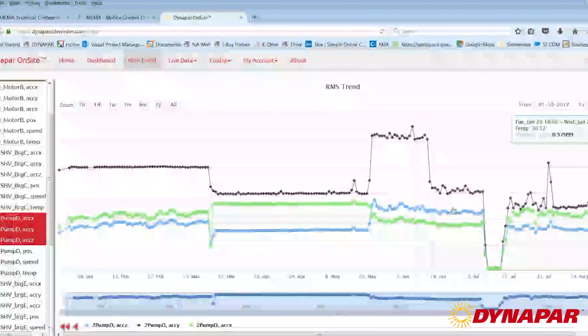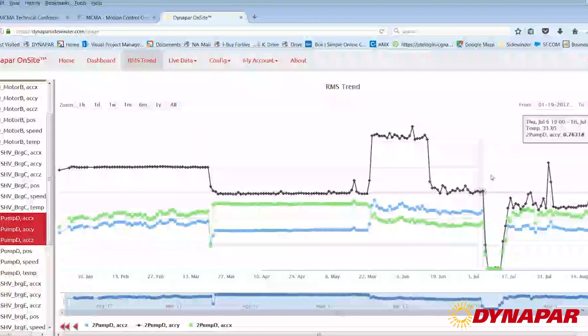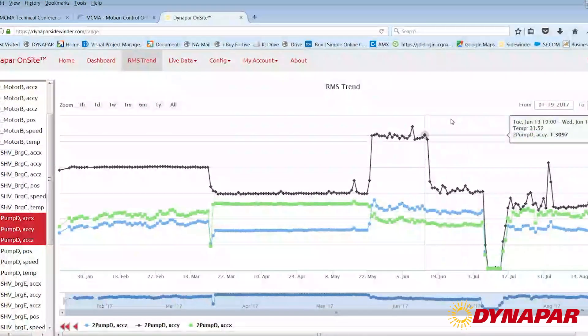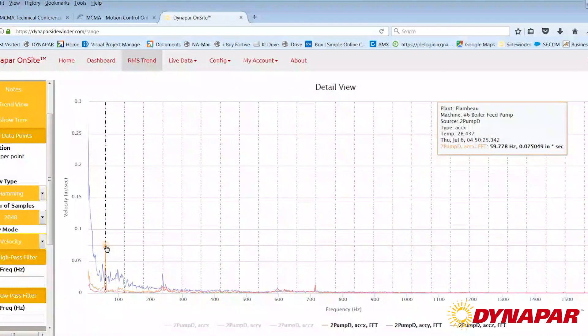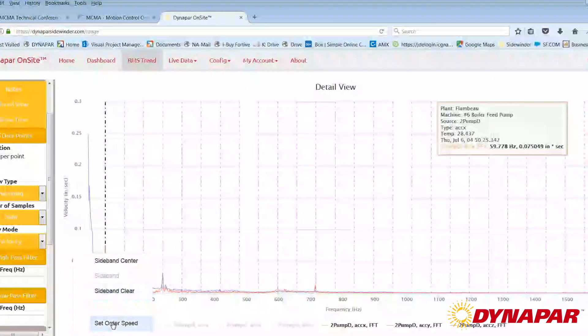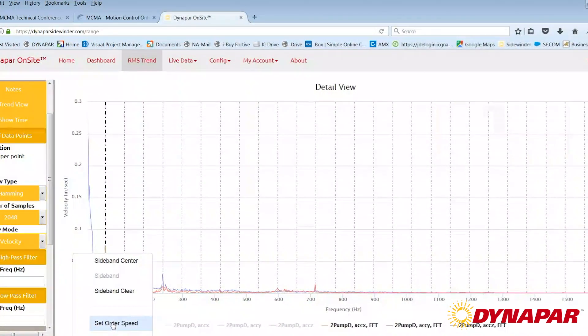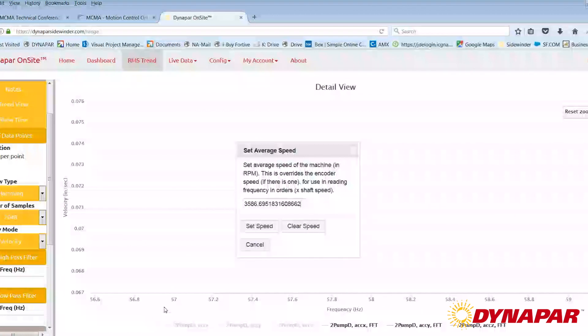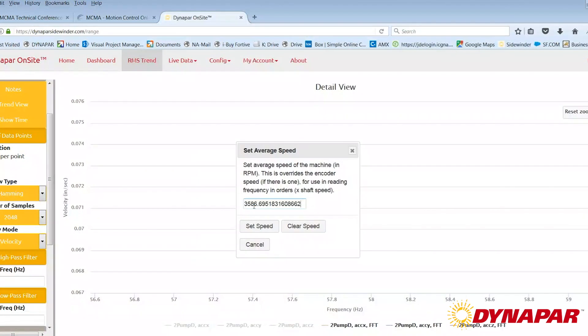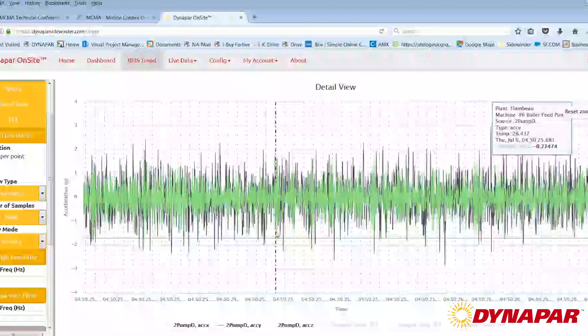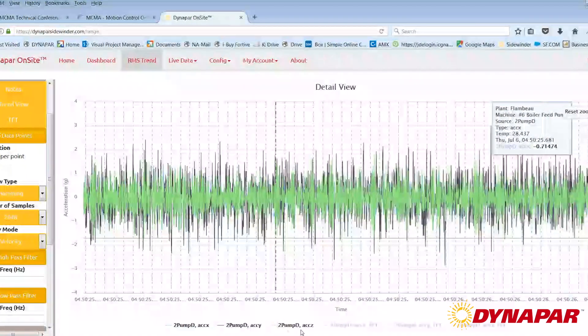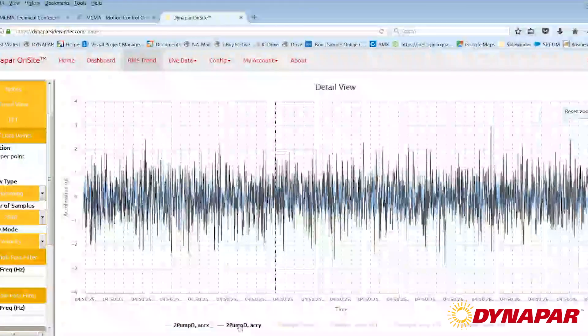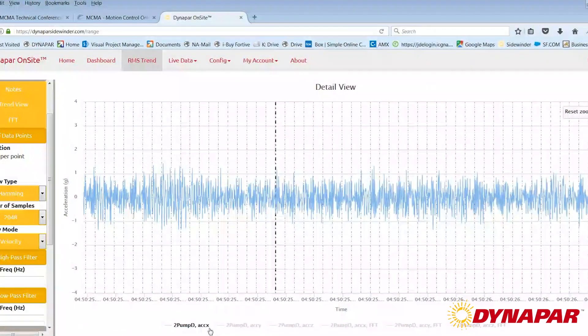Trend analysis is the key indicator to finding machine faults early by examining for increases in the amplitude of vibration. Once an increase in amplitude is found in the trend, looking at the FFT and analyzing the frequencies in the spectrum prompts the user on what type of discrepancies are present. If the problem does not present itself in the FFT, the time waveform may be used, which is the raw vibration data signal.